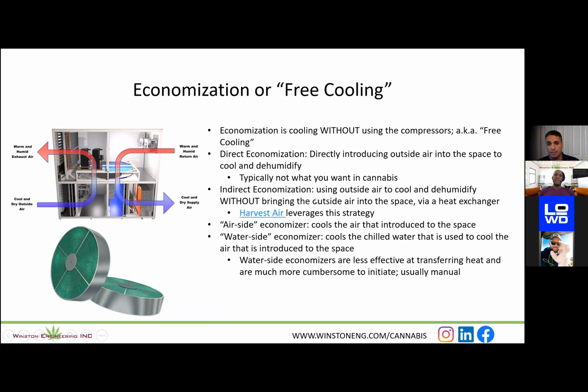So then there's what's called indirect economization. That's when you're able to use the outside air to cool and dehumidify without bringing the outside air into the space. And you do that via a heat exchanger. So what you're looking at here, this is a Harvest Air unit. This is the product that we sell. You see this wheel here, that's called a rotary heat exchanger. And in our case, that's specifically what's called an enthalpy wheel. That wheel is designed to absorb heat and humidity and transfer it, right? And it operates on a differential between this airstream and that airstream. So just from a high level, you've got warm, humid air coming back from the space. We run it through that enthalpy wheel. That wheel absorbs the heat and humidity out of that air, and then we send that air back cool and dry to the space. So in a completely separate plenum, here's your separation right here, you're going to bring cooler, drier outside air in, run it through that wheel, absorb the heat and humidity out of that wheel, and reject it to the atmosphere.